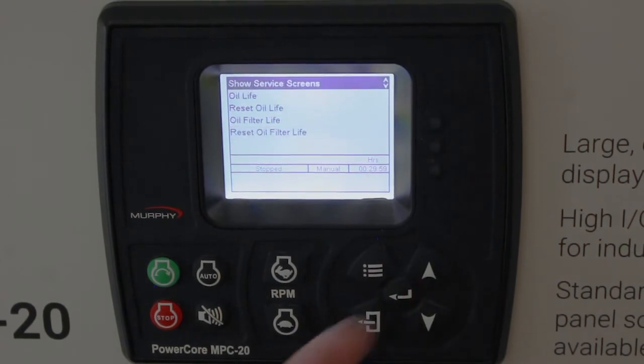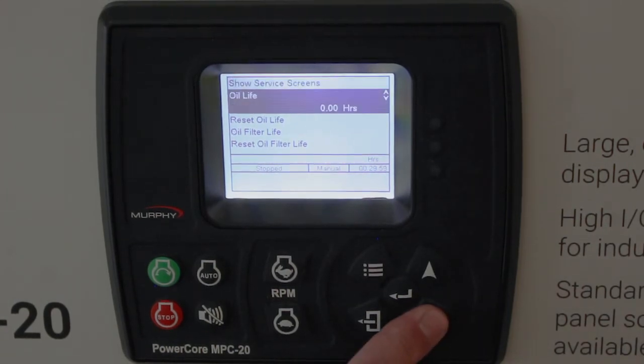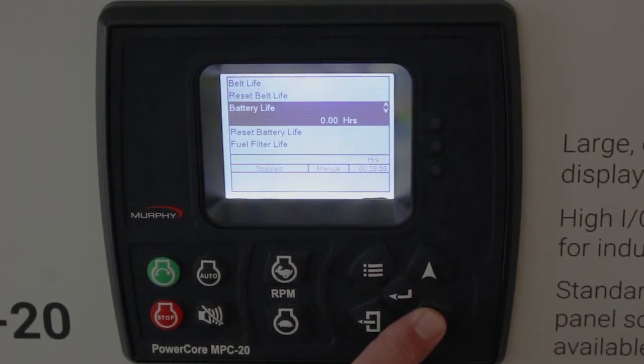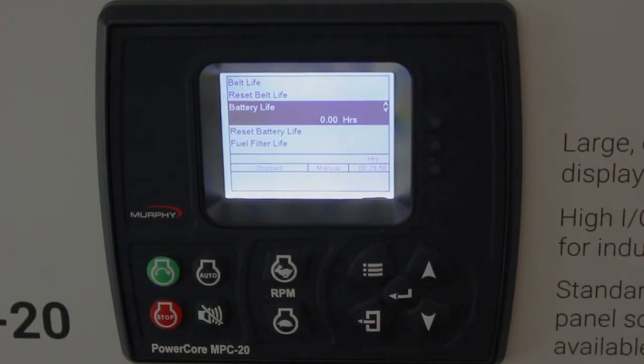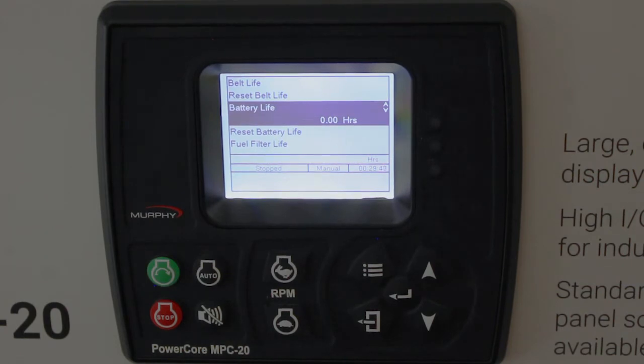Service reminders — you have many of them in here: oil, oil filter, belt life, battery life, and all kinds of service reminders that you can say yes or no to. All these have certain hours and are based on running hours. For instance, on battery life, if you put in 500 hours in this set point, 500 running hours later you would get a notice on the display saying to check the battery life.